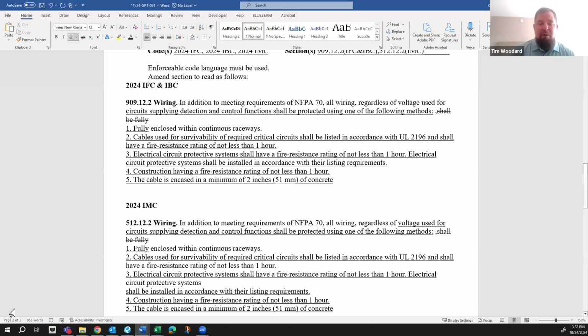Again, this is Tim. I'm hearing what Andy's saying, and it's making me think we should be very careful about accepting options 2, 3, 4, and 5. My immediate concern is, do I see a lot of 1 hour? But anytime we're 4 stories or more, we're going to have 2-hour protection of the shaft typically. So why wouldn't we be matching what the exit enclosure or the interior exit stair already is, versus just allowing 1 hour everywhere? I would like to see the proponent speak to this more, or someone else could shed some more light on why these are equivalent to a fully enclosed continuous raceway, then I think I would be willing to maybe take action.